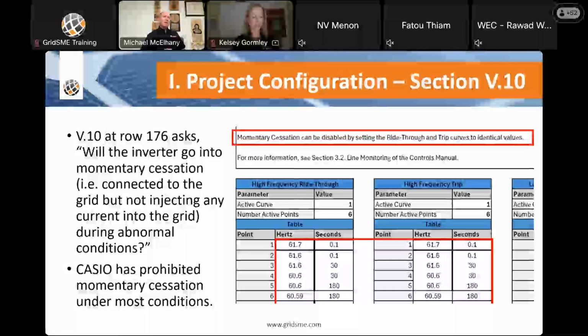Another inverter manufacturer has two flags, LVRT (low voltage ride-through) and HVRT (high voltage ride-through), and you either enable or disable those. If you disable those, that disables momentary cessation. And yet when CAISO initially saw that, they said, well, then you don't have low voltage ride-through enabled, and you have to have that enabled. So we had to go back and work with the inverter manufacturer and CAISO to make the link that this was their mechanism to disable momentary cessation.